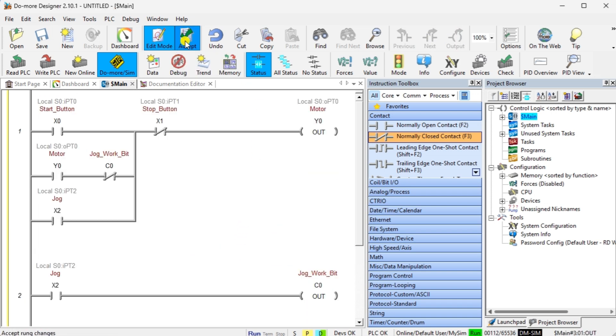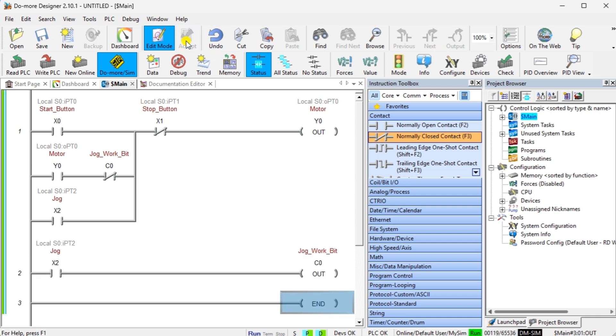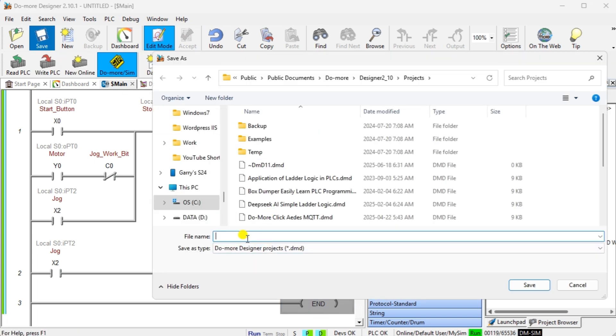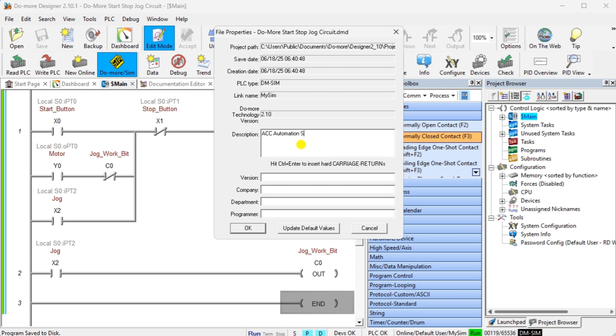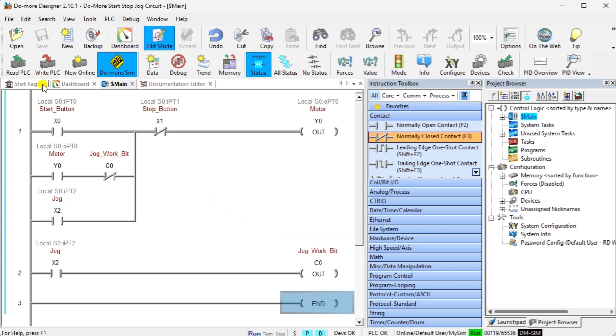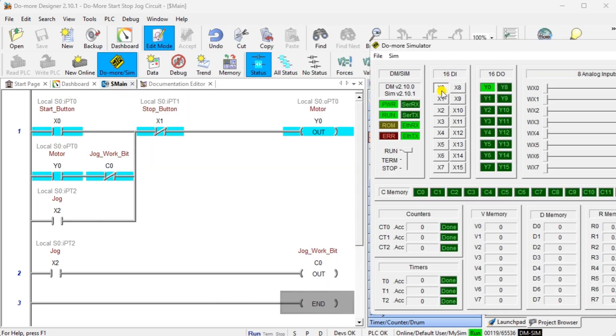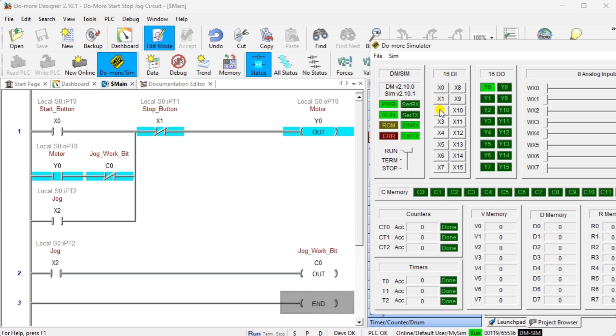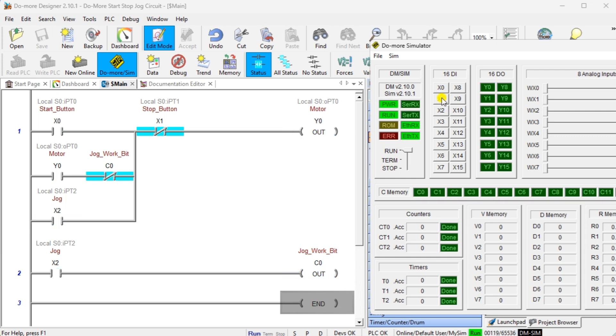Once we have entered our ladder logic for the start-stop-jog circuit, we can accept it. This will check the syntax of the code to ensure that no errors are present when it compiles. Use the Write to PLC icon to transfer our program. Select the status icon to view the status of our logic as it is being solved. We can now operate the inputs to ensure that our ladder logic circuit works. Since this is a fully functional programming software, we can use additional tools like Data View to see variables for our program. Since this software is installed on your computer, we can also use the simulator to communicate through the serial and Ethernet ports. This can test additional equipment on your system. The built-in simulator functions just like a physical Do More PLC (BRX), enabling you to immerse yourself in the world of automation.